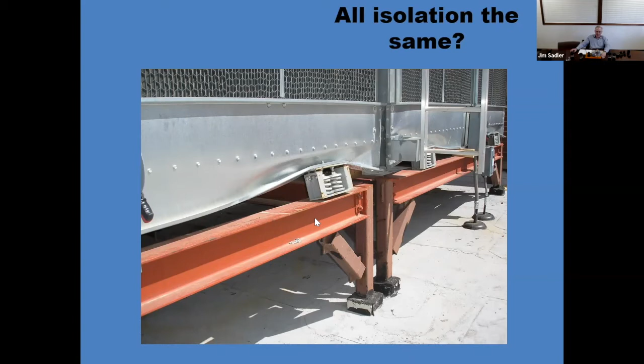Okay, then we get into seismic. So up to this point, we have a piece of equipment that's free floating. Everything's great. It's free floating. There's no oscillation. Everything's super. But then when an earthquake comes, if an earthquake comes, then you have the equipment free floating. It's actually holding up pretty well, but the structure can resonate with these springs and throw the equipment off the springs in a seismic zone.